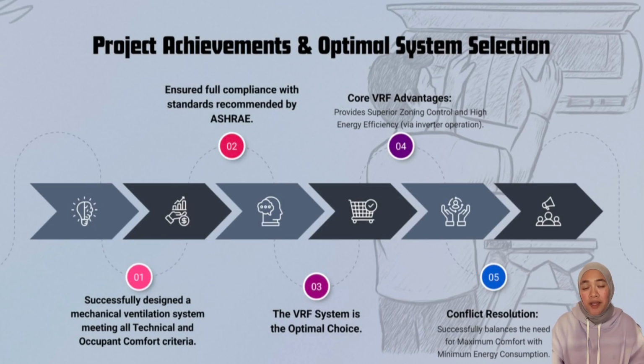We successfully designed a mechanical ventilation system that fully meets all technical criteria and occupant comfort requirements. Our chosen system is the VRF, Variable Refrigerant Flow system. This is the optimal choice. Why? Because the VRF system offers two main advantages: superior zoning control, which allows precise temperature adjustment for each office space individually, and high energy efficiency through inverter operation. More importantly, this design ensures full compliance with the standard recommended by ASHRAE. This is the success of our conflict resolution approach. We managed to balance the need for maximum comfort with minimum energy use.